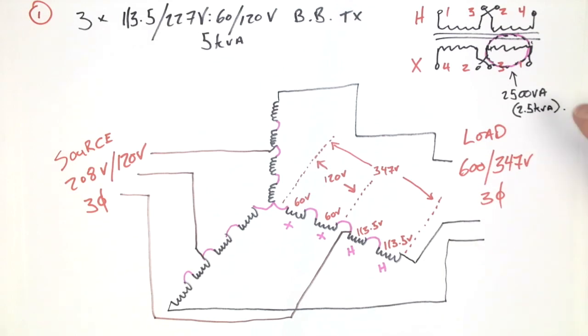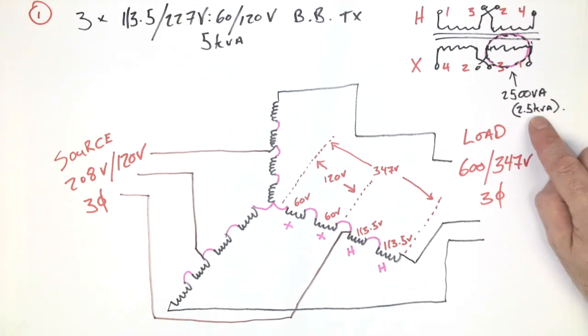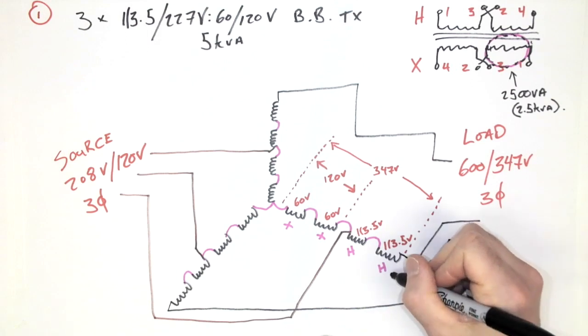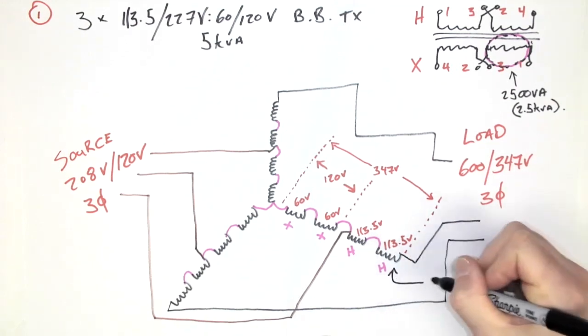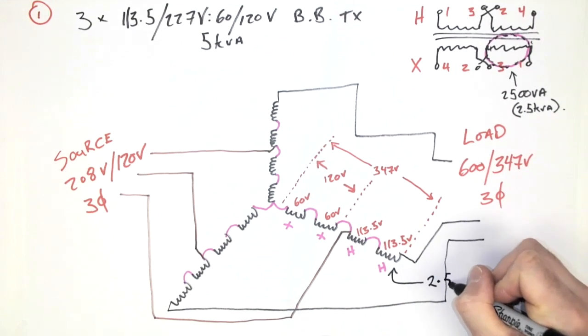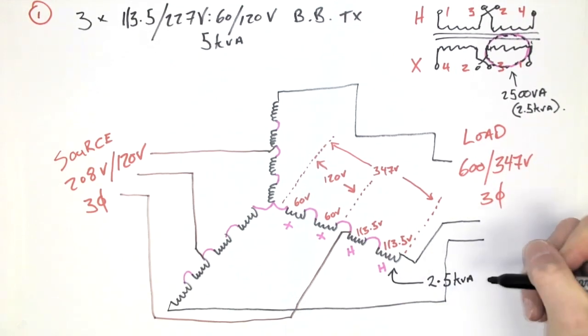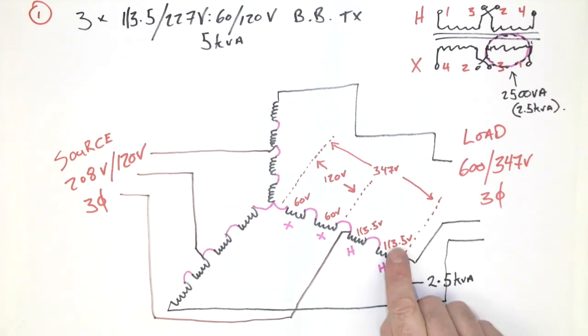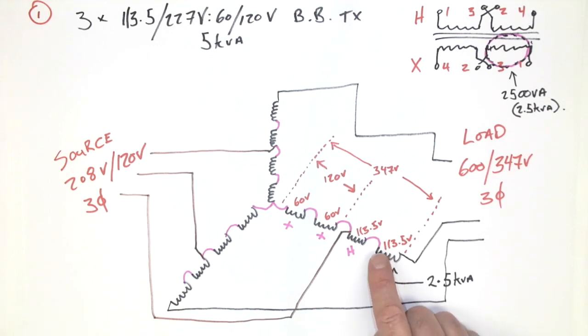Now, we said each winding is rated 2500 VA. I circled an X winding, but really it doesn't matter which winding we're looking at, it is rated 2.5 kVA. So that means this winding here is rated 2.5 kVA. I'm going to use this information along with the voltage to determine the maximum amount of current that this winding is able to carry.